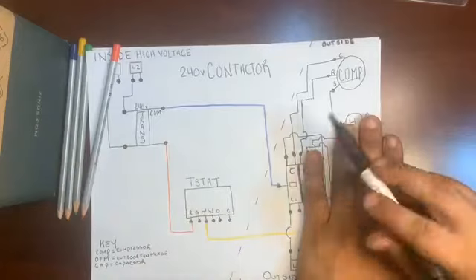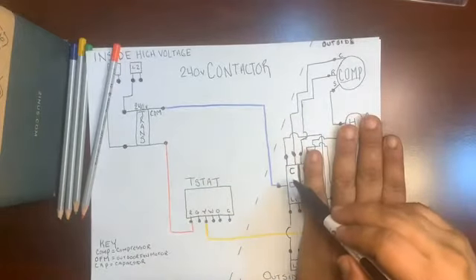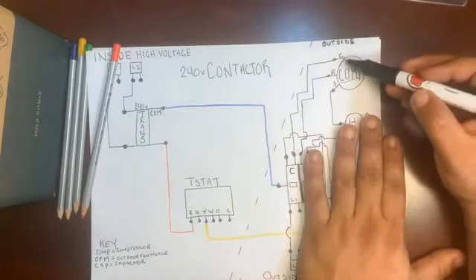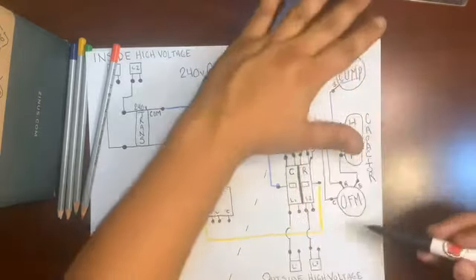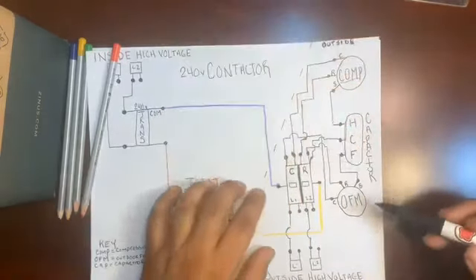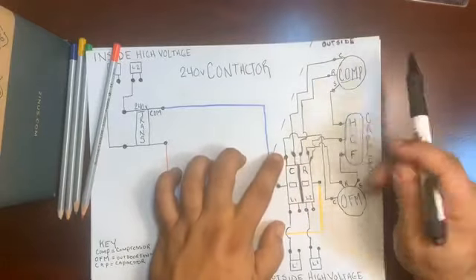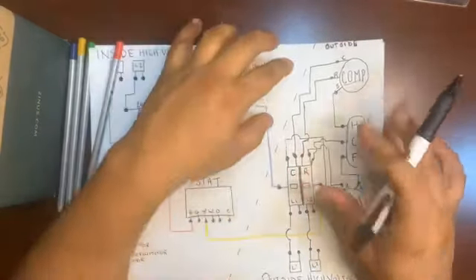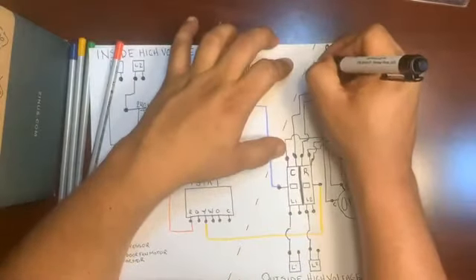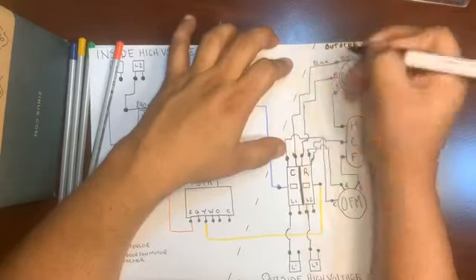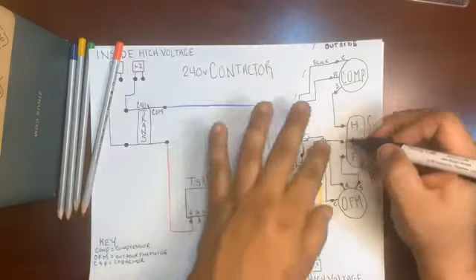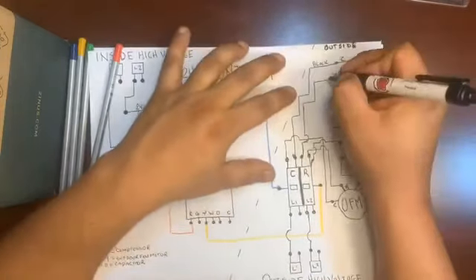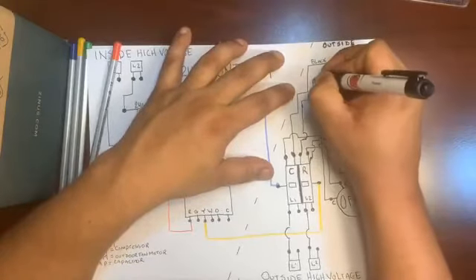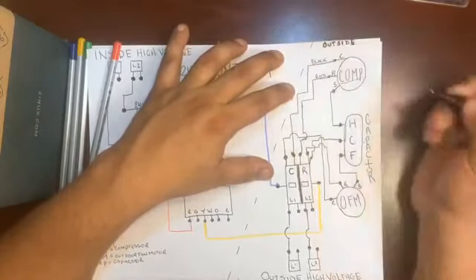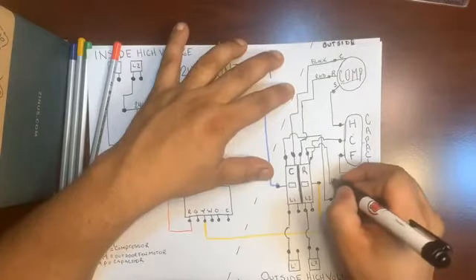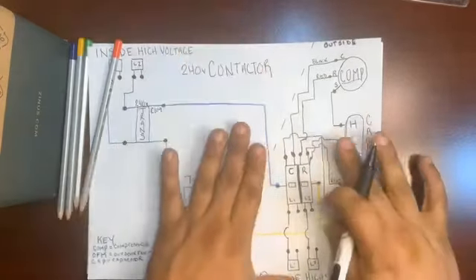You think it'd be the common side, it's not. The common side of the contactor is strictly reserved for the common leg of the compressor and the common leg of the outdoor fan motor. Those are the only things that are going to be on this common. Traditionally, in almost every system you're going to get to, this common is almost always going to be black. Sometimes your run colors will change from red to yellow, but in that case the red on the compressor would be run, and down here this run would be red as well. So they try to make this color coded.